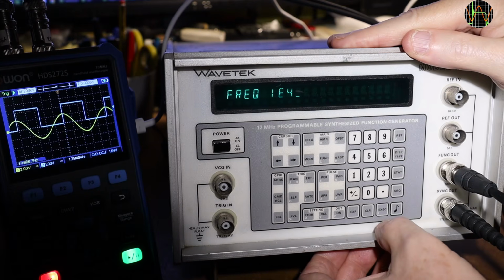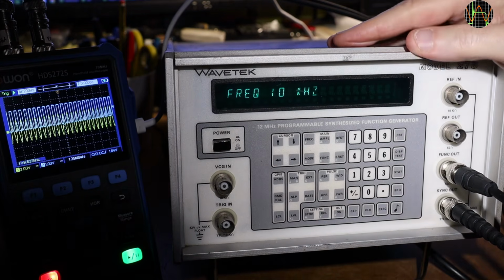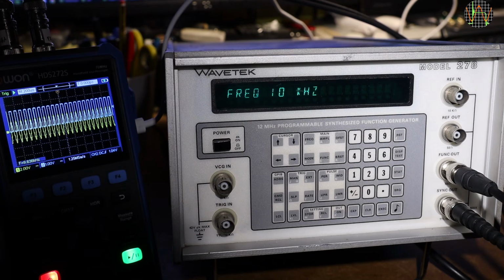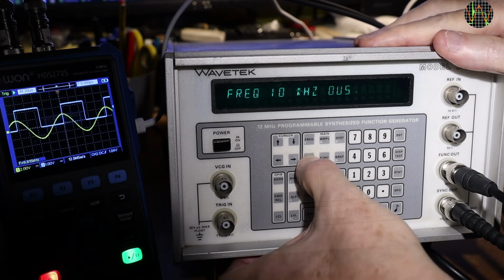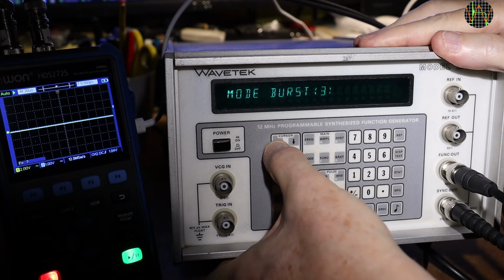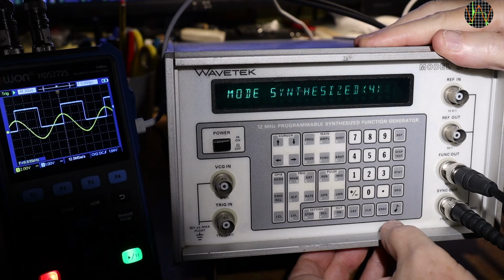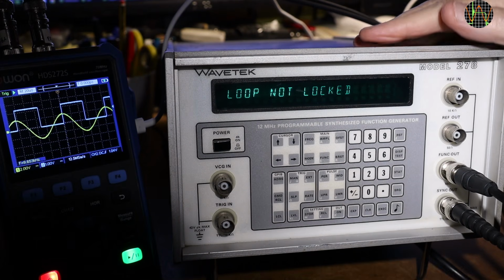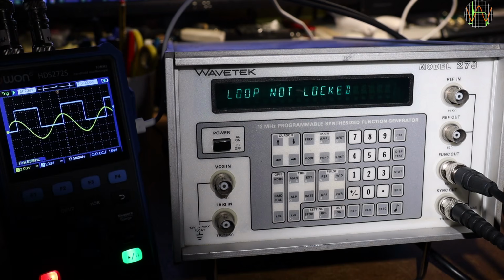By default, the generator frequency is selected by a microprocessor, switching appropriate range capacitors and, within a range, a processor-generated voltage, because the generator is voltage controlled. This method is used in continuous mode, triggered, gated and burst. The fourth mode is synthesized, and if I execute mode change to 4, I get an error, loop not locked. The synthesized modes for 4 and above do not work. Moreover, the QA procedure only checks modes 0 to 3, so it might have been so for a while.